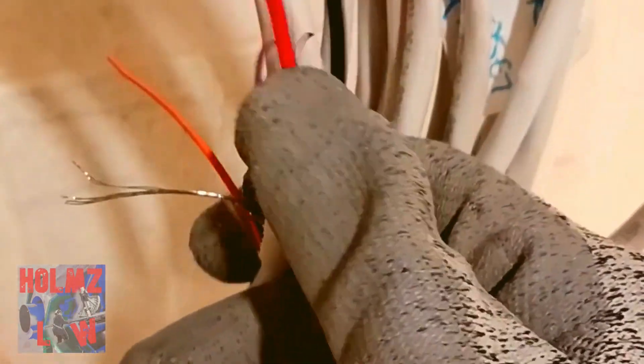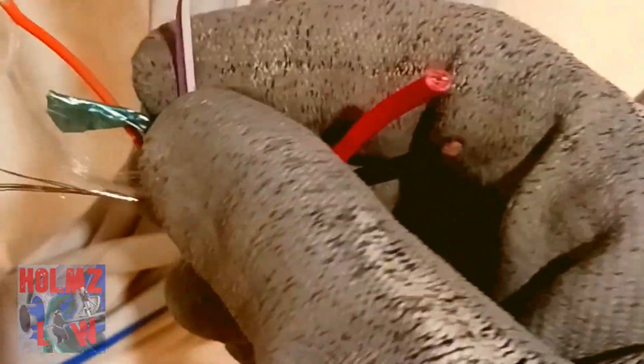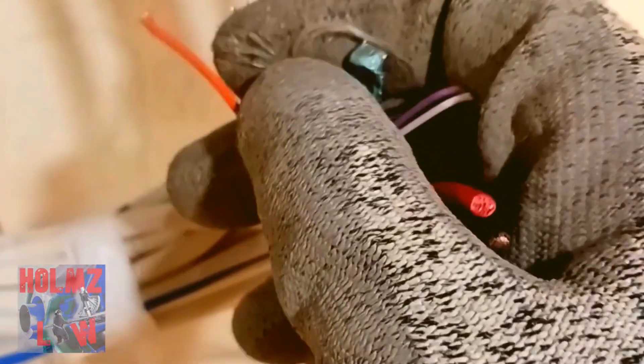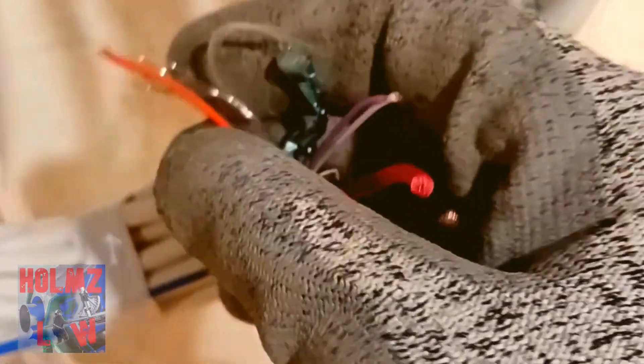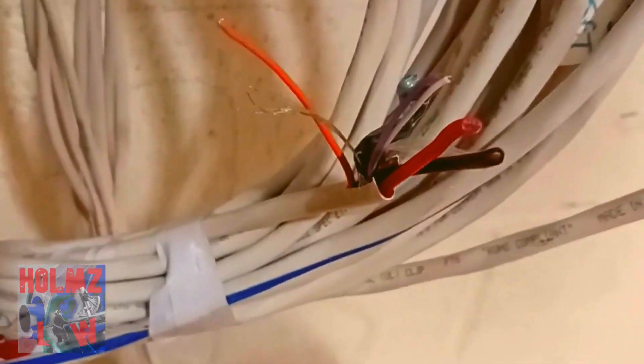This is my QS link cable. It has two 14-gauge wires for the 24-volt, and then it has some 22-gauge wires as well. It also has a little ground wire. The orange wire is not connected in this instance — it's not used here, but in other instances you can use it.